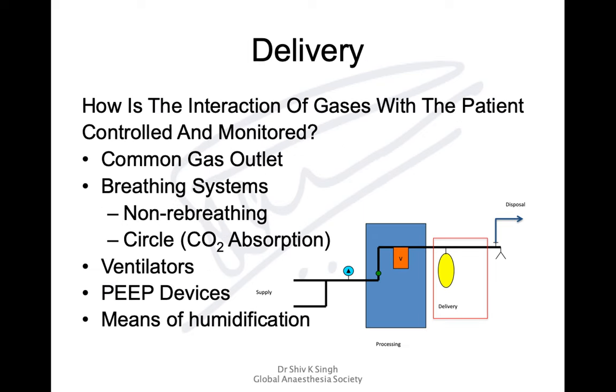Delivery is about how the interaction of gases with the patient occurs and how these are controlled and monitored. There is a common gas outlet to which breathing systems are attached — these can be non-rebreathing or rebreathing circle systems. Ventilators drive the gases for the patient instead of manually squeezing the bag. Additional PEEP devices can be attached, and there can be means of humidification, though a circle system makes this less necessary.